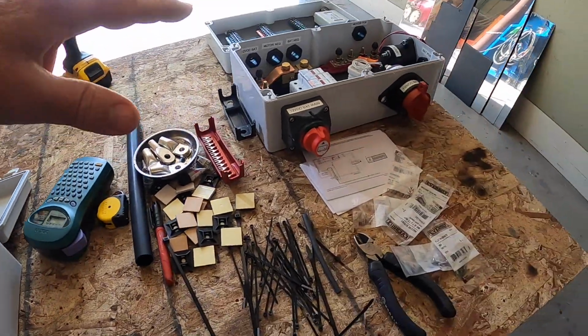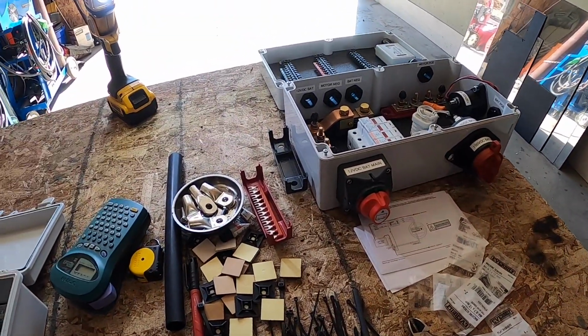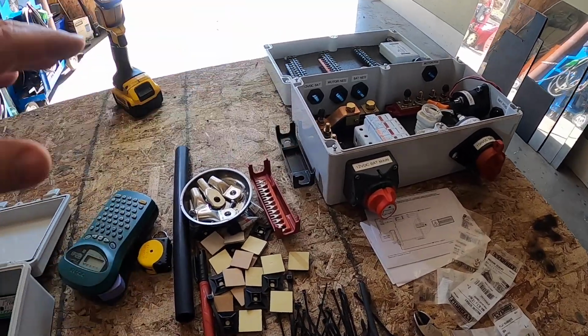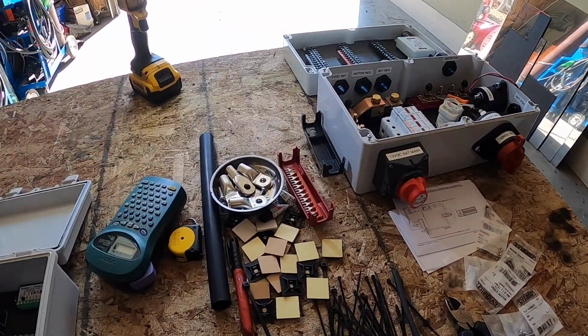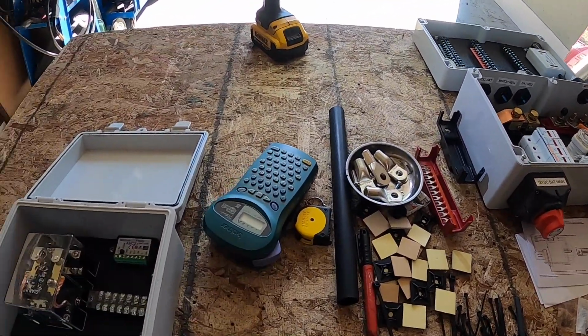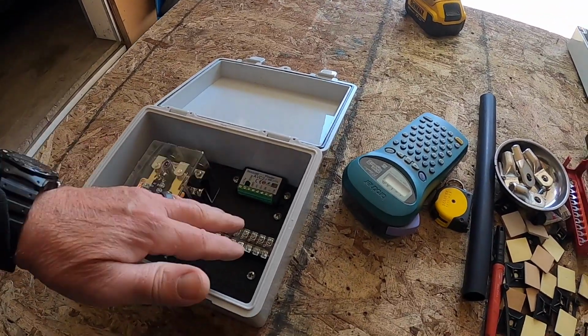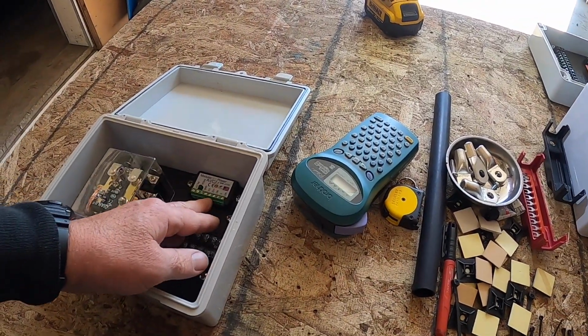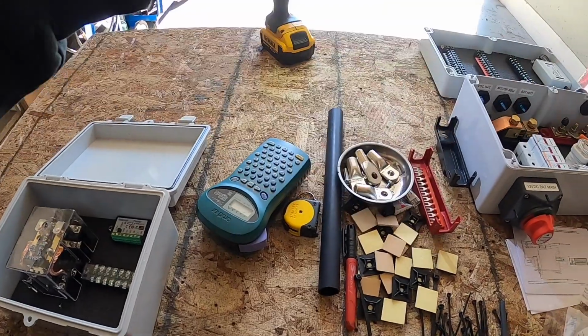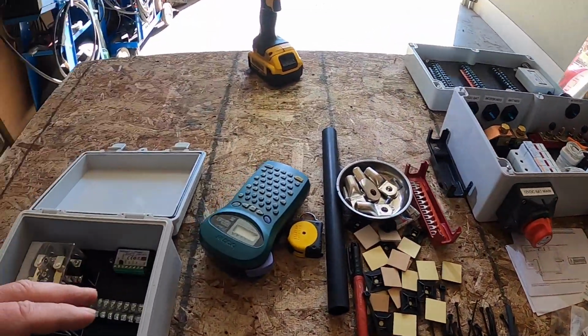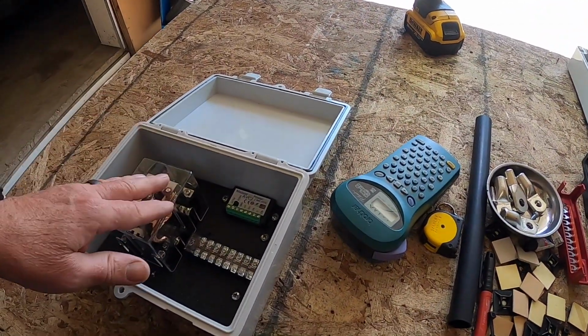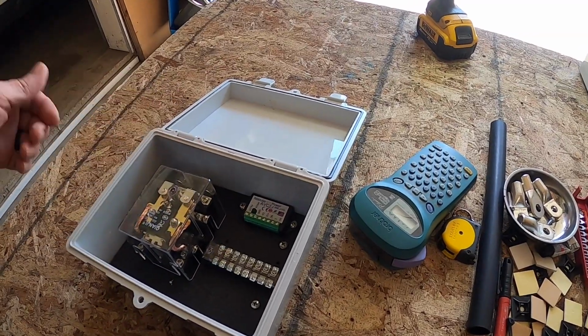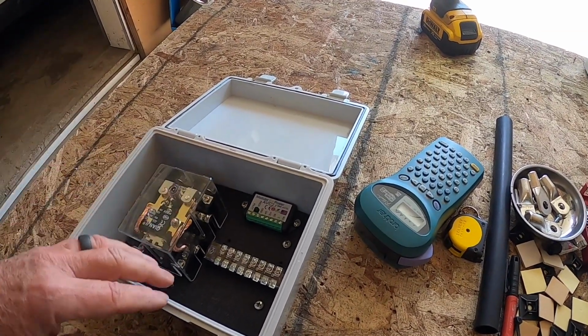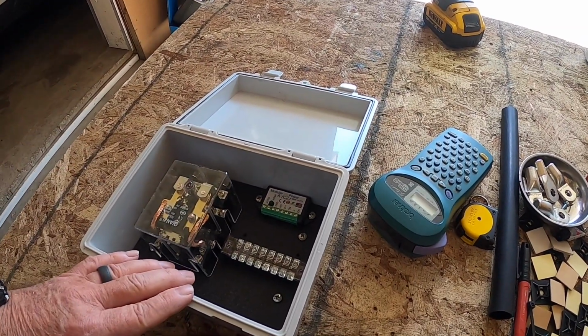In addition to the CAN bus control from the BMS to shut off the chargers, shut off the motor and all that good stuff, there's going to be CAN bus communications between everything. This is going to be an analog way, so if I get up to 150 volts and the CAN bus maybe has an error in communications, I could also have an analog shut off that will kill the battery charger and create a little safety in here.